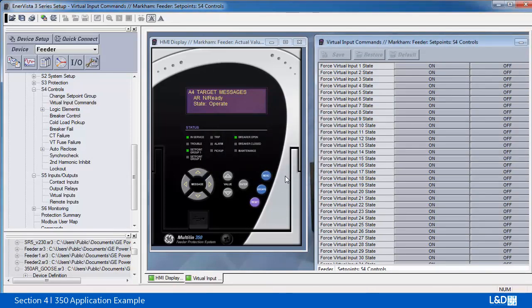I heard the relay click, and now I see the status is in the closed position. The breaker is closed, and I can reset the front panel trip. From the target message, I see AR ready, so it's ready to do the auto reclose. So now I'm going to ramp up the current from the RTT and wait for the auto reclose to start.